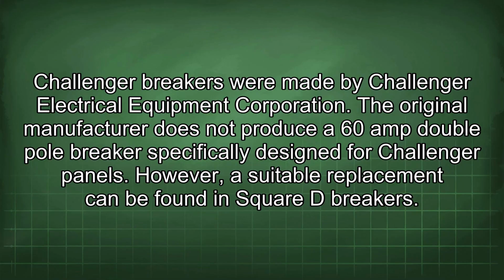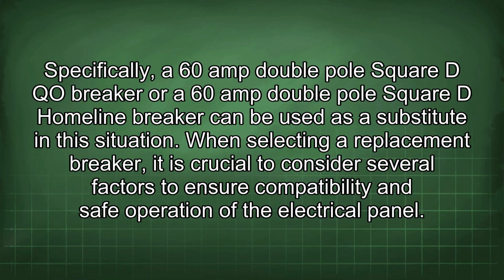Challenger breakers were made by Challenger Electrical Equipment Corporation. The original manufacturer does not produce a 60-amp double-pole breaker specifically designed for Challenger panels. However, suitable replacement can be found in Square D breakers. Specifically, a 60-amp double-pole Square D QO breaker or a 60-amp double-pole Square D Homeline breaker can be used as a substitute in this situation.